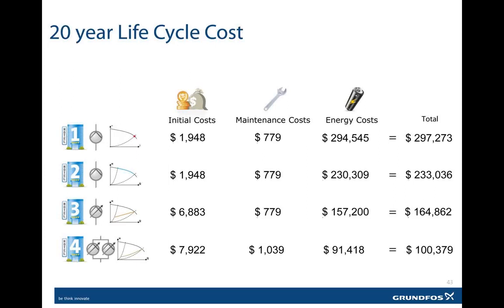Now when we look at the initial cost for the Magna 3, although our initial cost would be higher for the pump at $6,883, even if maintenance costs were the same, which again they wouldn't be for a Magna 3, now our energy costs are reduced to $157,200 for a total life cycle cost of $164,862.